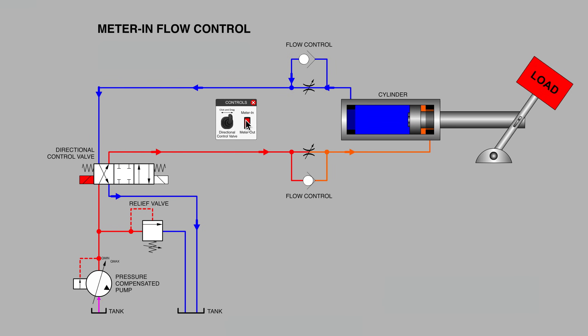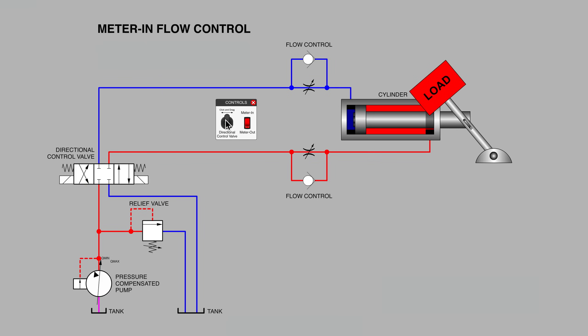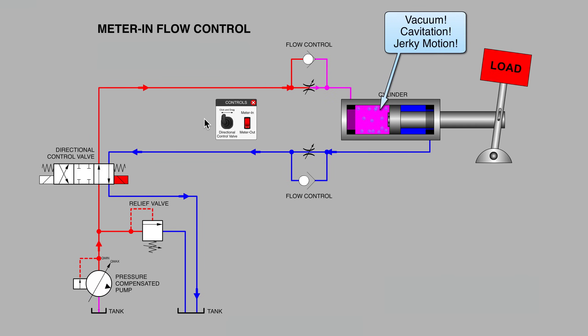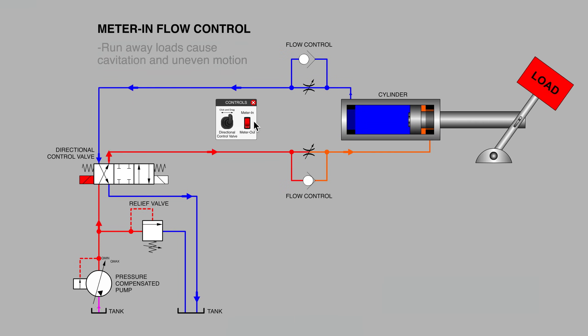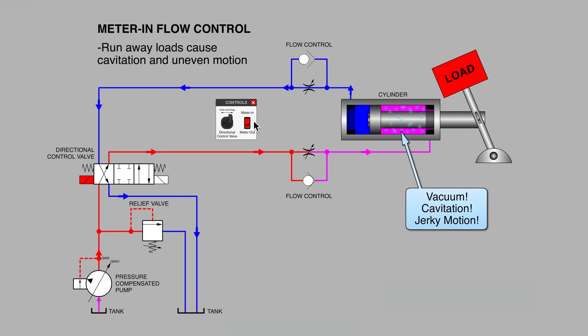What we find out is that it's working well until the point at which the load goes over center. And then the cylinder rod is being moved perhaps a little faster by the load running away than the pump and valve can supply to the cylinder, and hence the very uneven motion that we're seeing and perhaps even the formation of some cavitation void in the cylinder. A very uneven motion with plenty of undesirable effects.